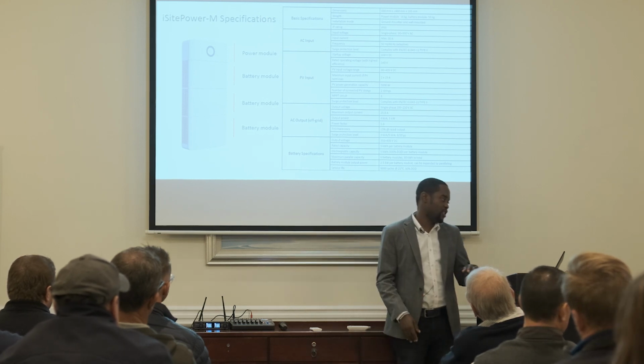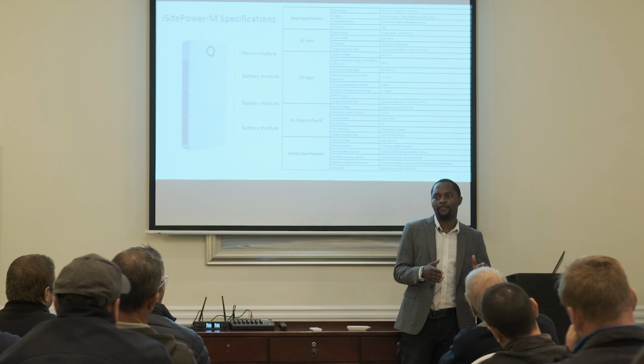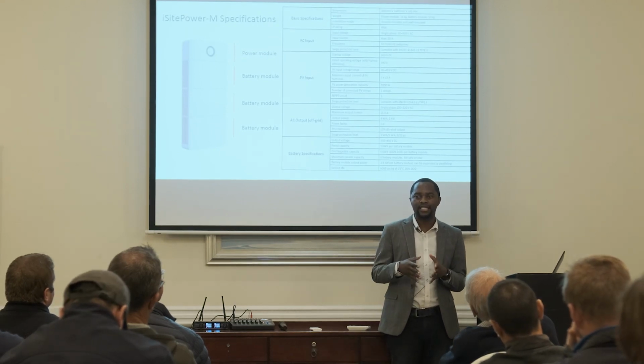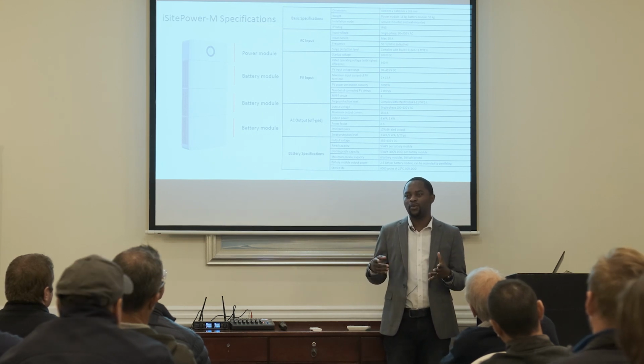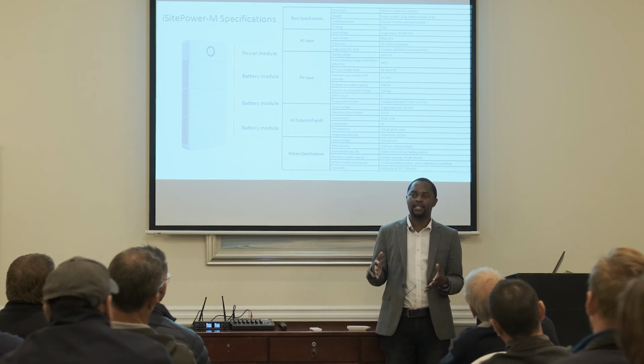You can use almost any panel size on this unit, right? So the operating voltage for the MPPT is from 90 to 435, and then the startup voltage is 100. So you need at least 2 panels, or 3 to be safe, for you to start up the MPPT. Otherwise, if it's less than 100 volts, then the MPPT won't wake up and start operating.